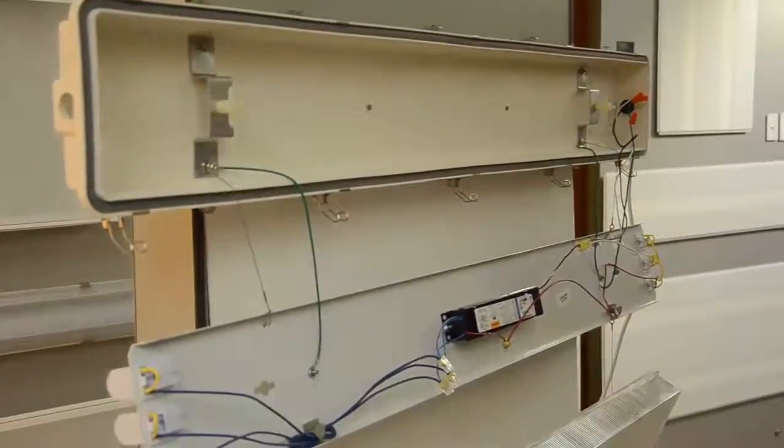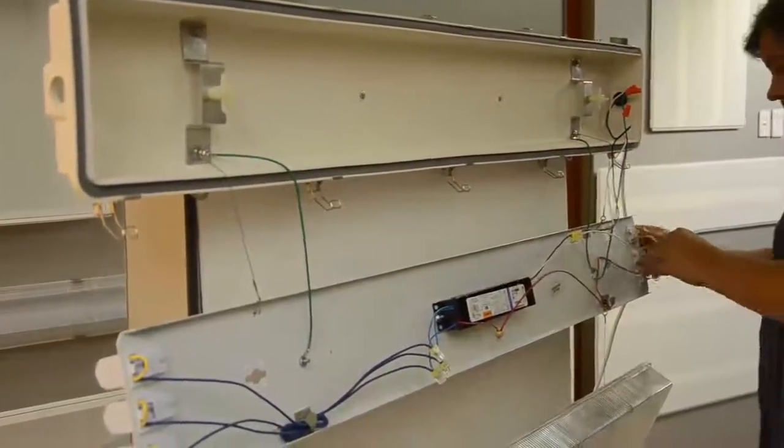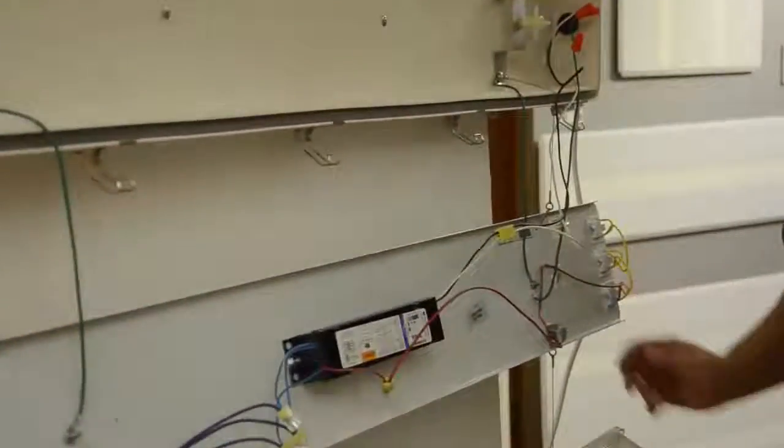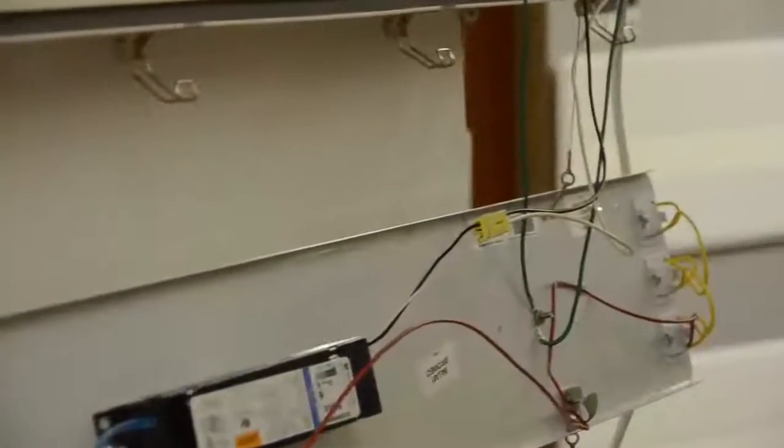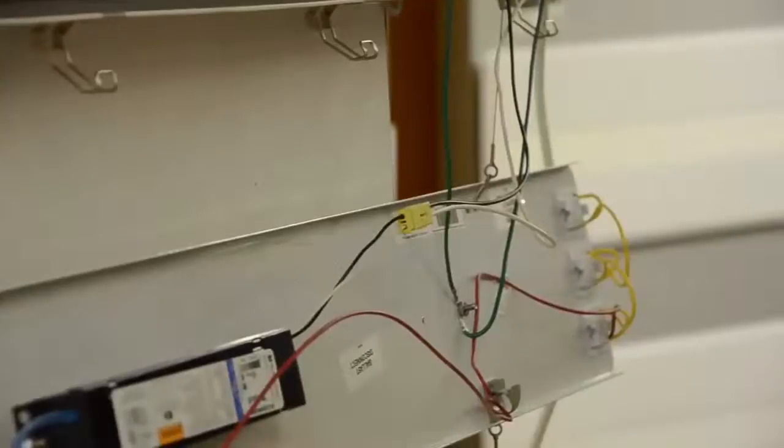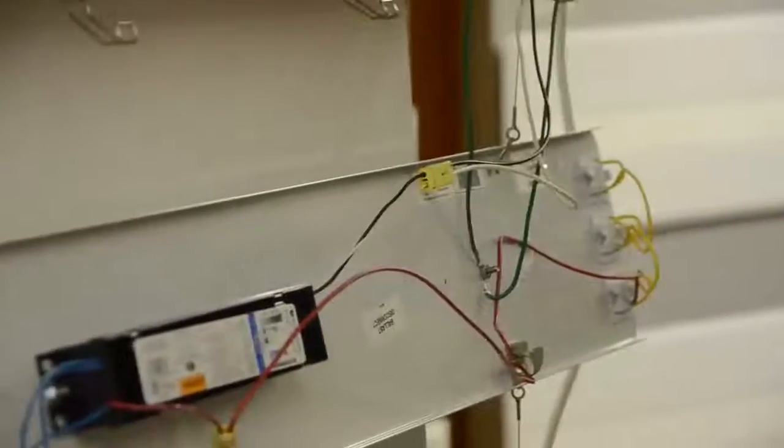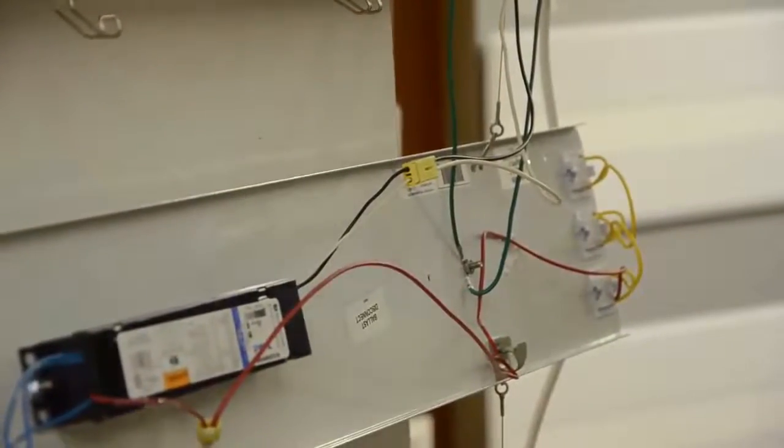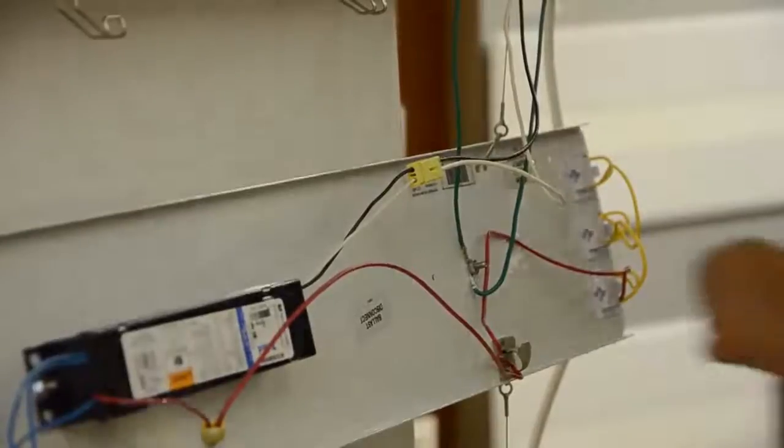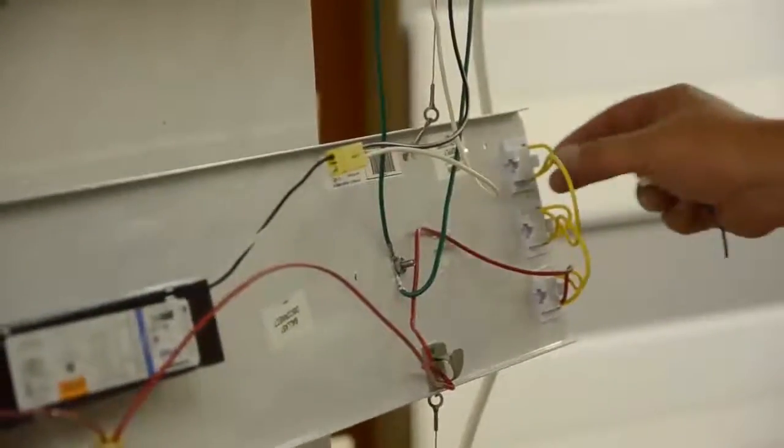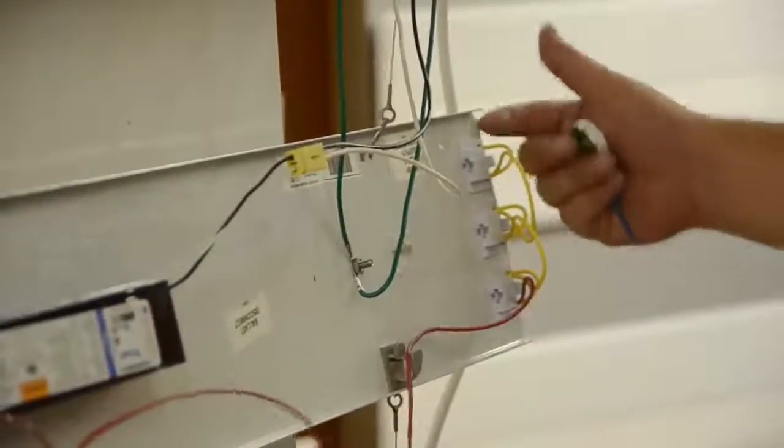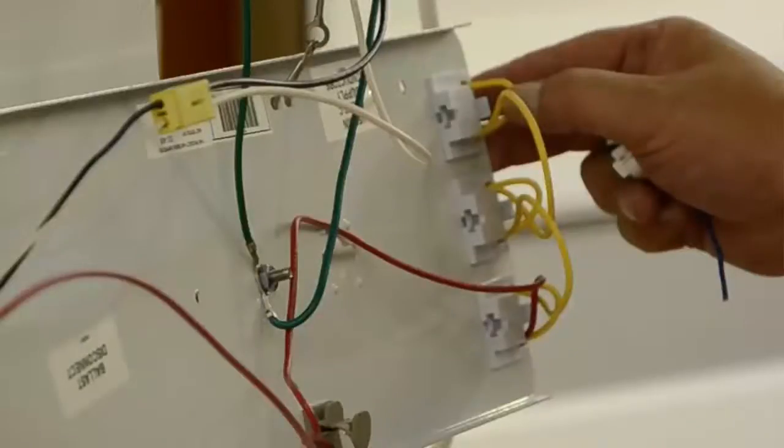First, we're going to identify our sockets. Clearly, these sockets are shunted sockets. The MaxLite internal driver LED T8 requires non-shunted sockets. This socket is clearly shunted because you can see there's a connection wire that connects both sides of the pins on each socket.